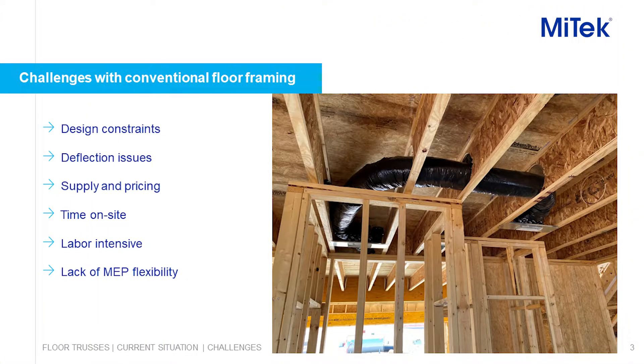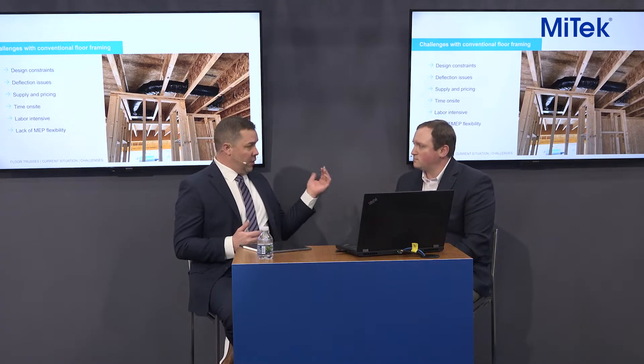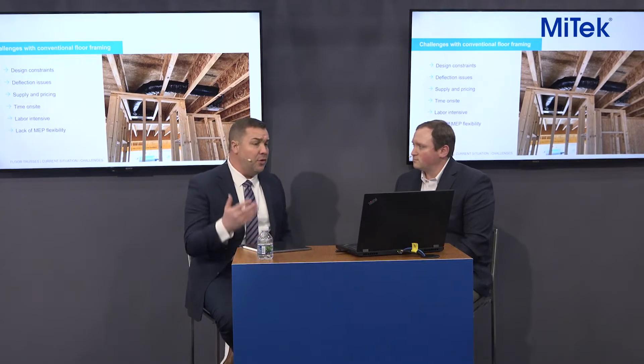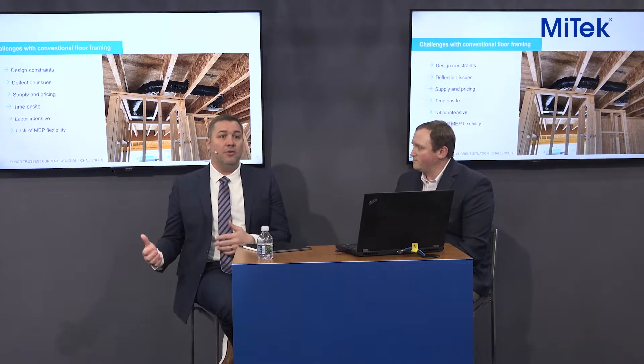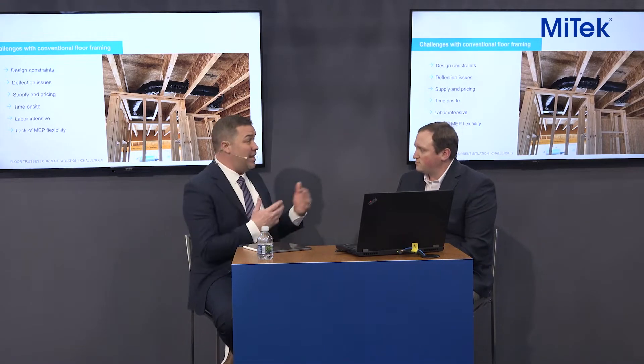This picture on the screen is a great example of how you can get efficiencies through MEP installation. If you look at that flex duct, I counted nine 90-degree angles on that run. Every 90-degree turn is the equivalent of 50 straight feet of run from an airflow perspective. If you can run the HVAC flex duct at a 45-degree angle through the floor trusses, you can reduce airflow, reduce CFM, reduce your air handler size, and even reduce the size of your condenser.